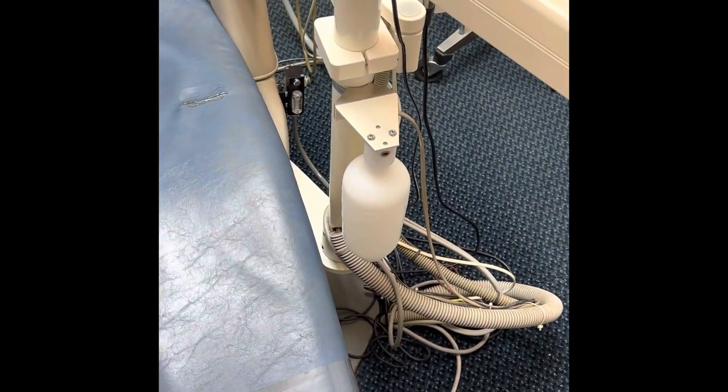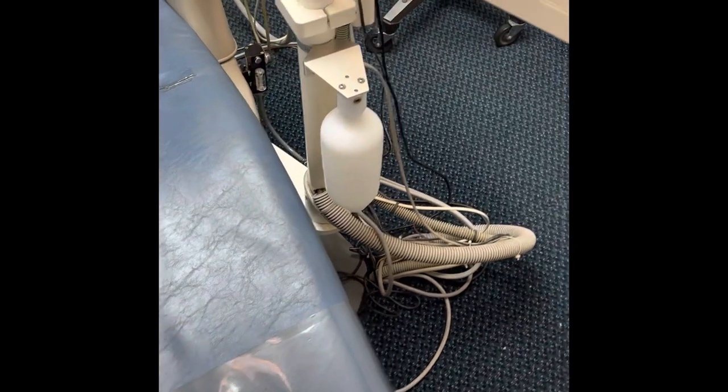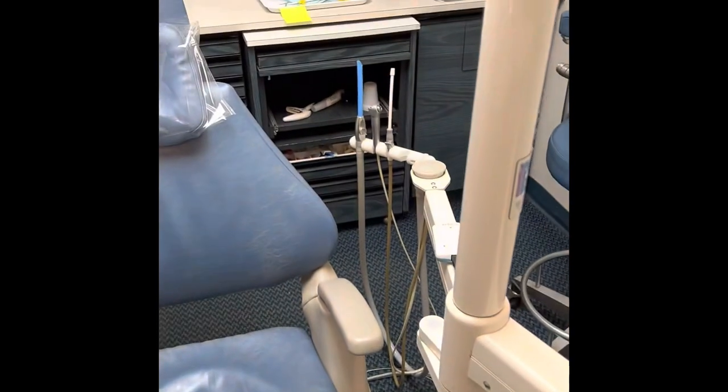I already changed the bottle manifold and it didn't fix the problem, because that's the main point where the air and water can mix. I actually just got done changing two manifolds at this office. The other air-water syringe right there does not have the symptom, and when I was troubleshooting I came to the...